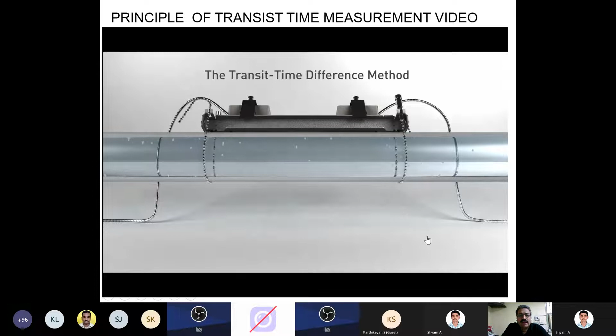So the transit time difference method exploits the transmission speed of the ultrasonic sound signal. Similar to a swimmer swimming against the current, the ultrasonic signal moves slower against the flow direction. For the measurement, two ultrasonic pulses are sent into the medium. One is in the flow direction, the other one is against it. The pulse, the pulse again, you can see the time.